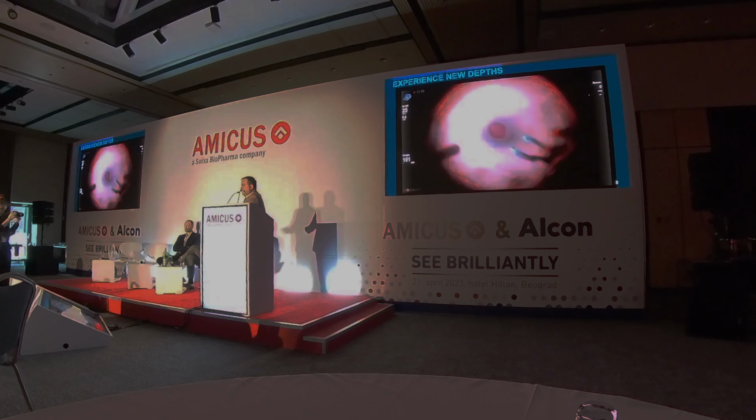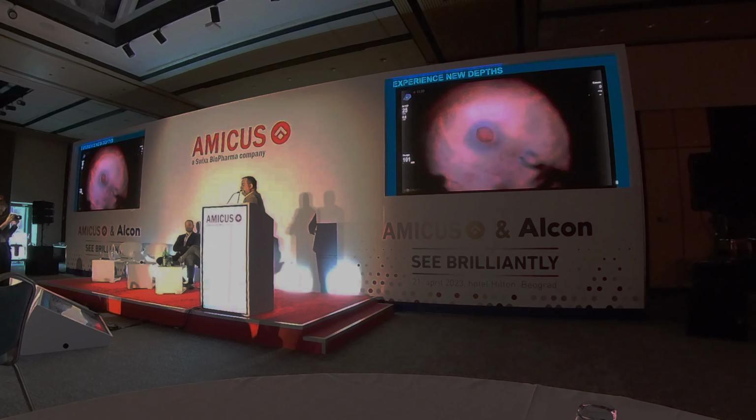Next thing to show is the depth resolution phenomenon. You see the edges of the macular hole and the overall length of my forceps, which is in focus. This is on maximum magnification of the microscope. When we are on maximum magnification, we have shallow depth of field. This is purely optical law. So here you can appreciate the depth resolution.